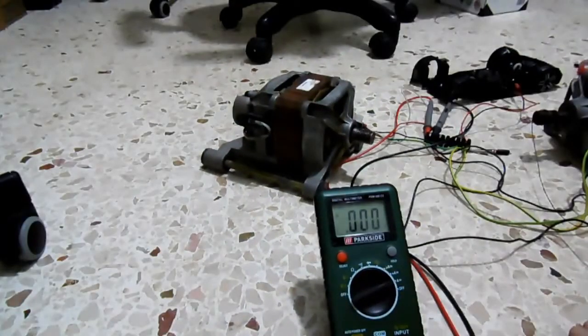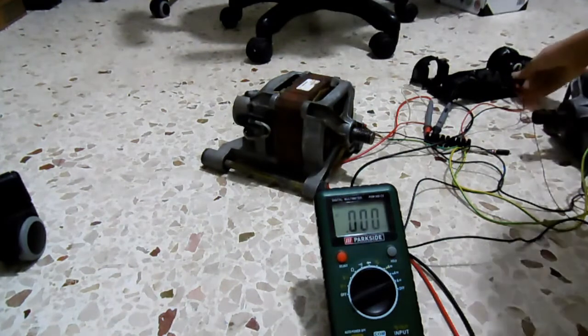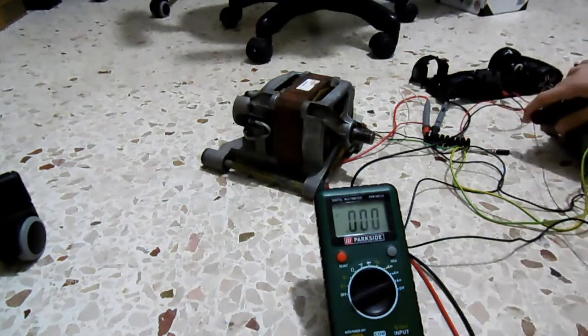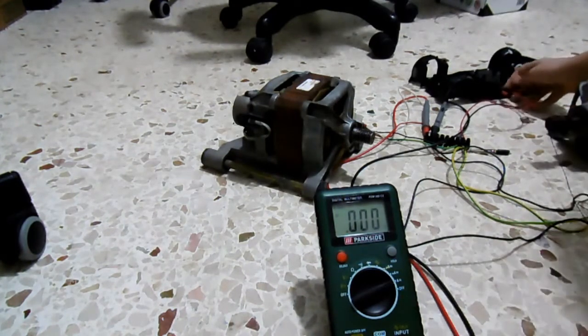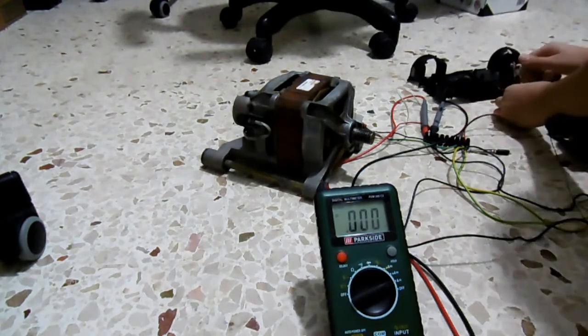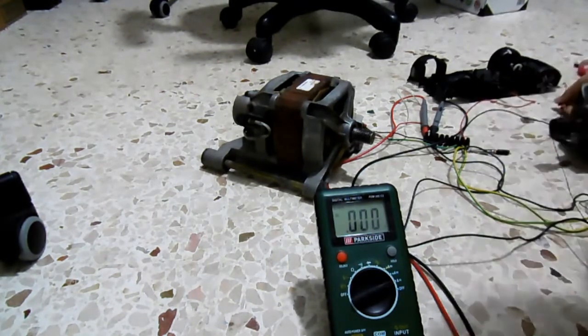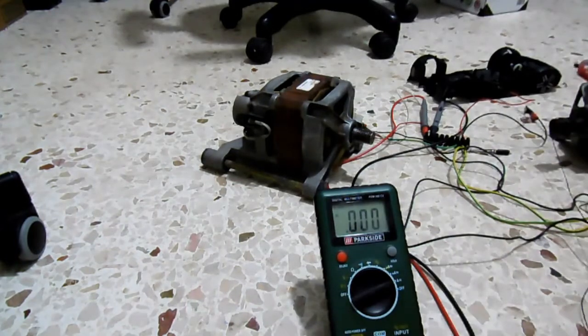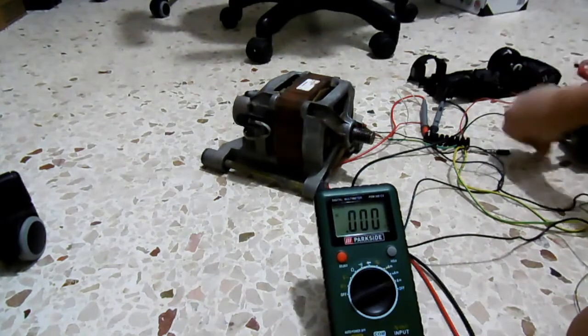Now, of course, under short circuit the generator is going to be extremely hard to turn, and I may either hurt my fingers or probably destroy something. So there's another way: I don't load the generator, or don't feed excitation, and turn it at high speed, then suddenly connect the load or excitation. That's a pretty bad idea when it comes to the load, because if I short circuit the generator while it's turning at high speed, it can cause an explosion, and yes, it won't end well.